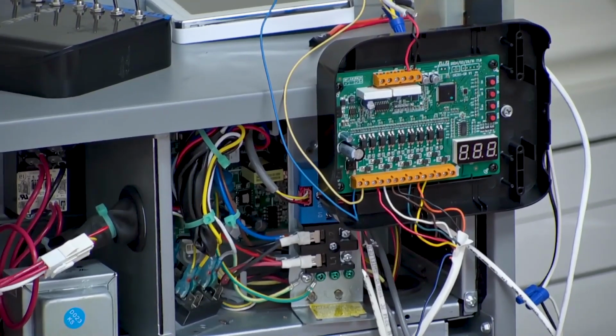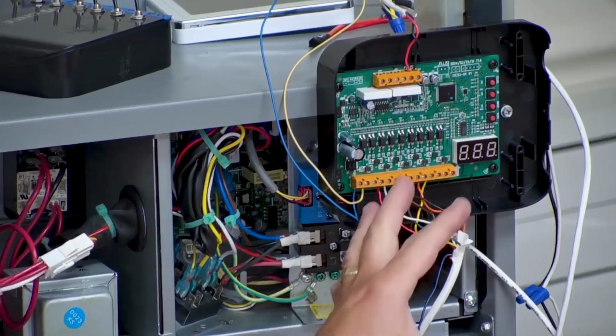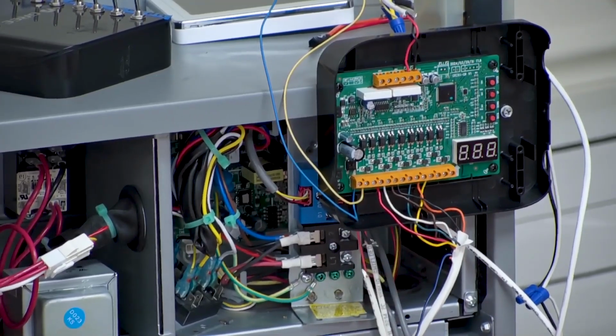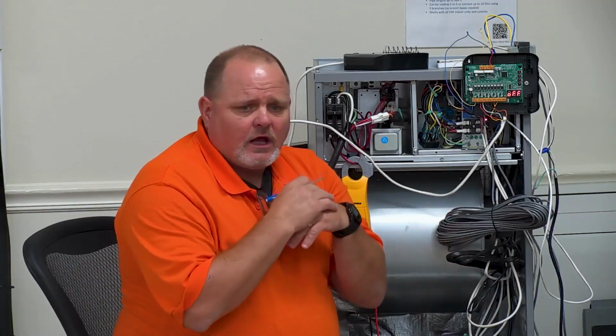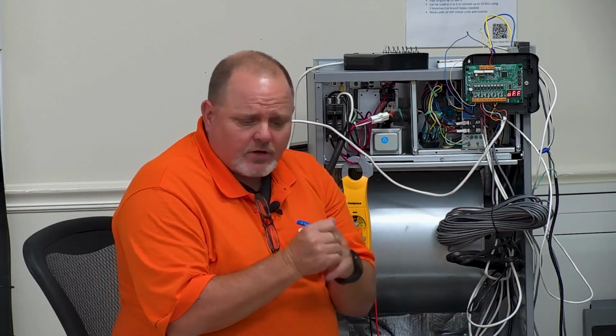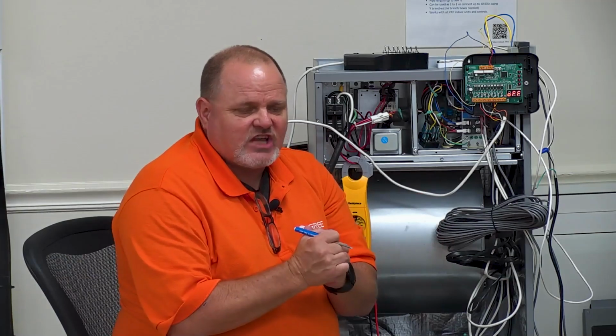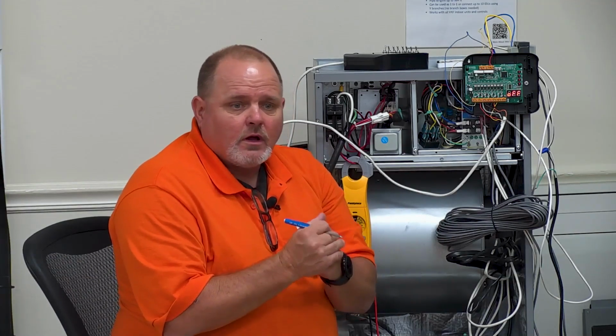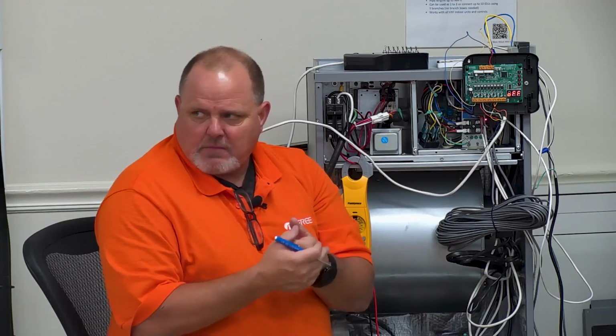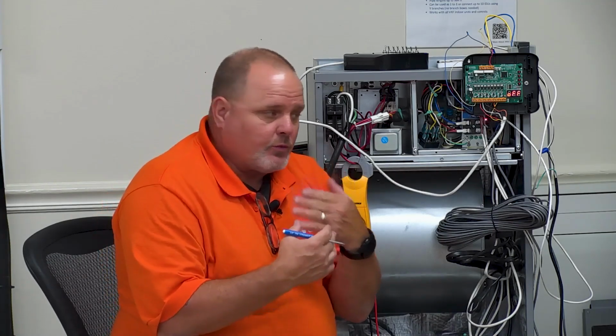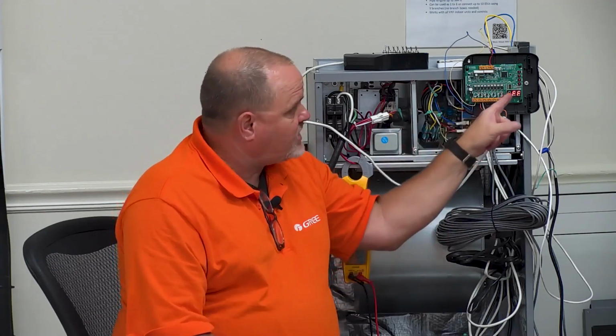Correct. So what that means is, this is whether or not you want this controller to be the master indoor unit. So especially, let's say you've installed the MultiPro system, you've put the GREE wired controller on there, you've done all the startup, you did the debugging, everything's up and running, but it's running on a GREE wired controller. And let's say that GREE wired controller for that particular air handler was set at the master. Here's what could happen to you. You go in here and you install the 24-volt adapter.